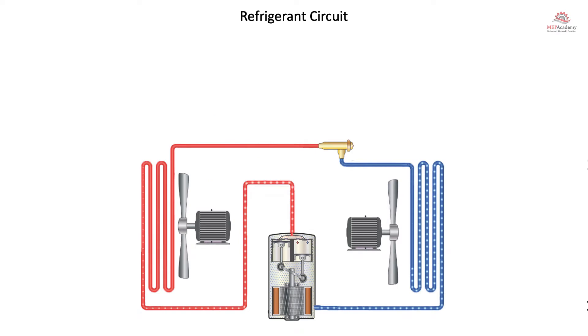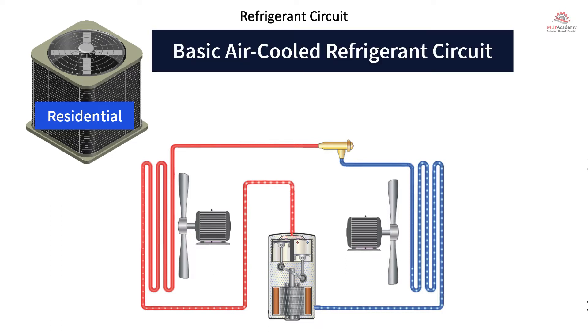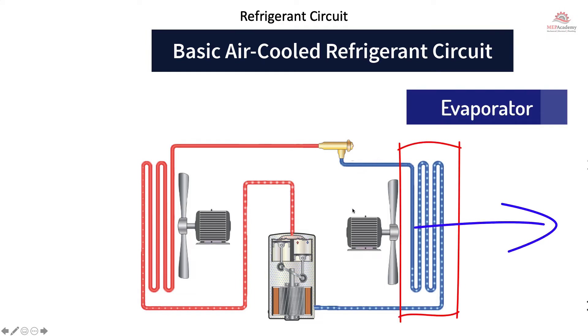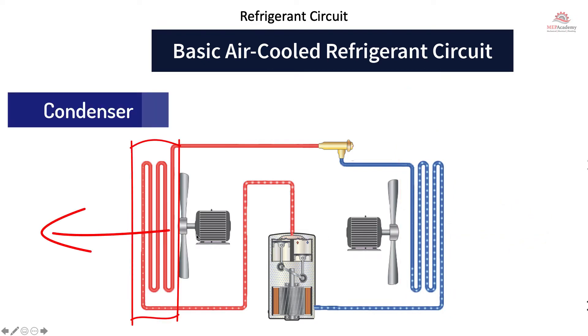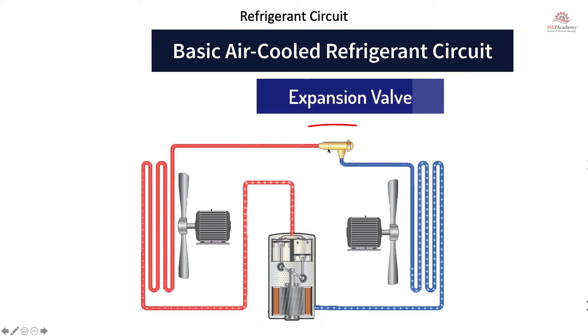The refrigerant circuit for a water-cooled chiller and an air-cooled chiller is somewhat similar to your home air conditioner. In a typical refrigerant circuit, the four components found in just about every refrigeration system are: the evaporator coil with a fan for air cooling, the condenser coil with a fan blowing over it, the compressor which moves the refrigerant around the system, and the expansion valve or metering device that controls the amount of refrigerant flowing from the high side to the low side based on demand.